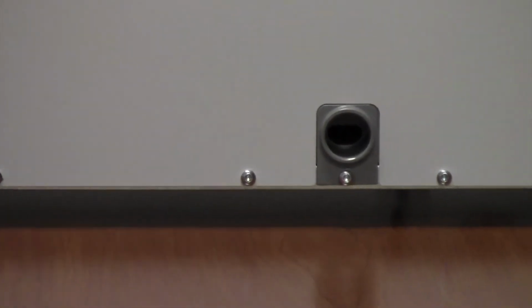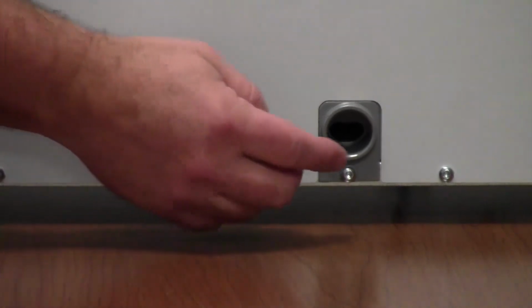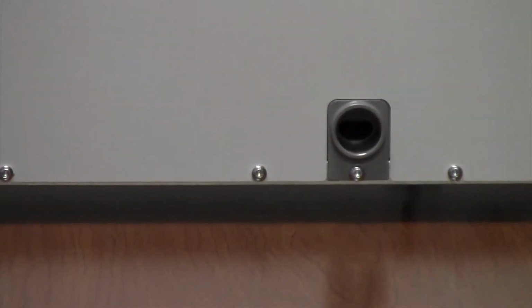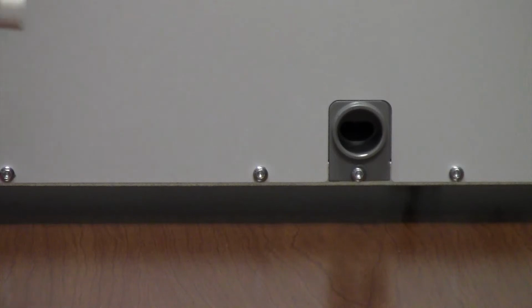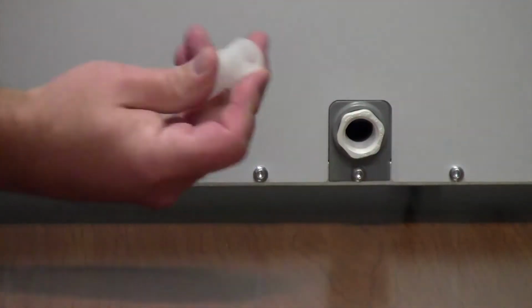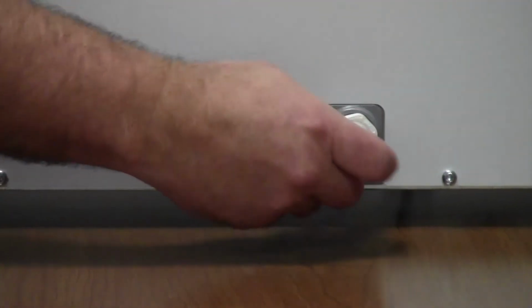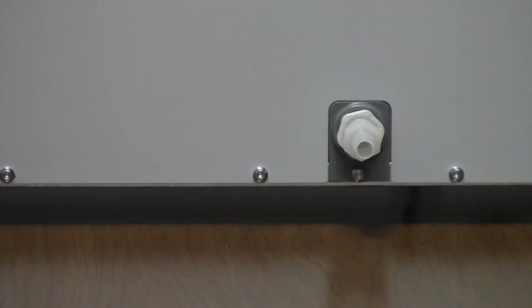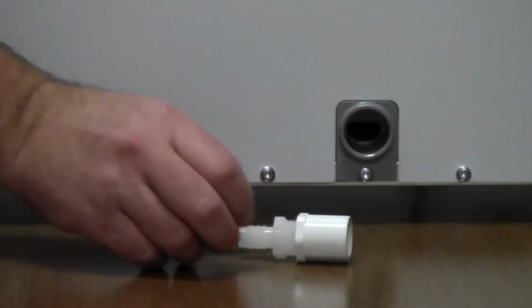Again, these are positive pressure cabinets, so there's no need for a P-trap. This drain connection, you can glue in 3/4 inch PVC pipe right in there and use that directly out of there. Or if you want to use 1/2 inch vinyl tubing, we have a little glued in piece that you can insert there, and then you'll have a threaded barbed fitting for 1/2 inch vinyl tubing. So you can do either option.